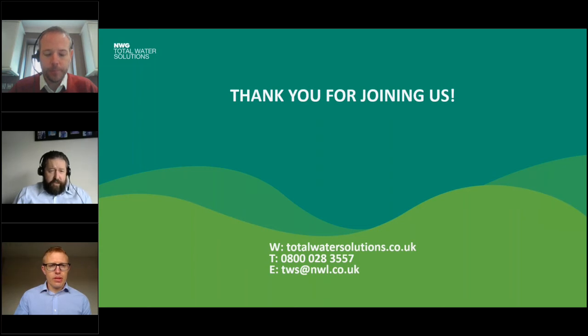Brilliant. I suppose that takes it on: when you were saying it's calibrated within 1 to 2 degrees, does it need calibrating continuously throughout, Mark? No, not at all. We've built it into the system. We've mapped the performance of what each sensor should be, and we know the drift exactly over the 10-year battery life. There are automatic alerts built into the system, so we get notified if any of the sensors come out of that calibration and spec. There's also self-checking every week between the sensor and the gateway it's attached to, and they all check each other with cross checks to make sure everything's in line.